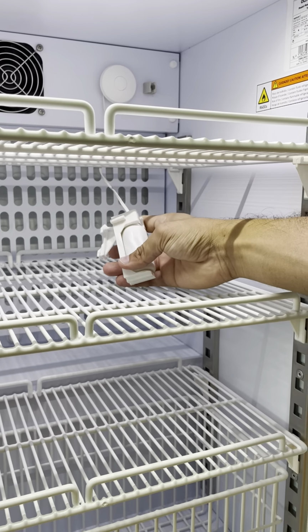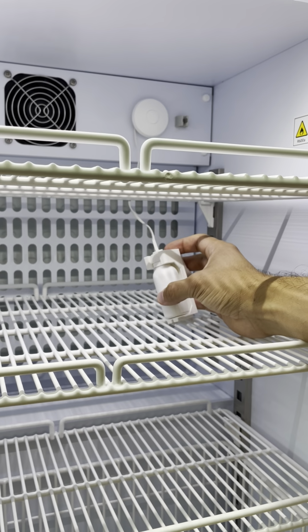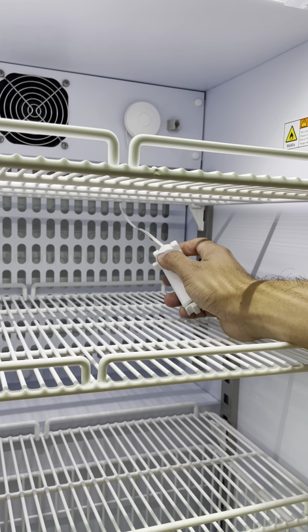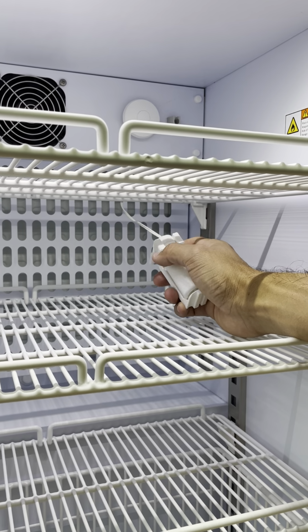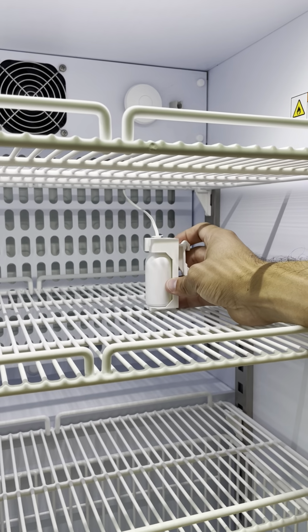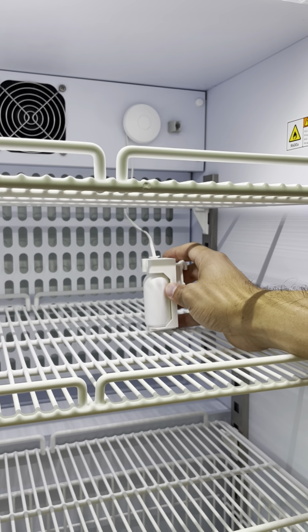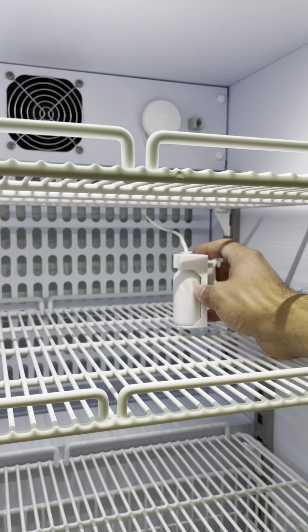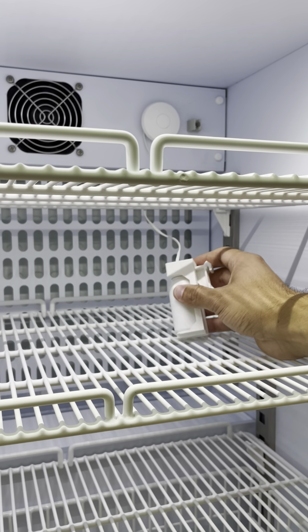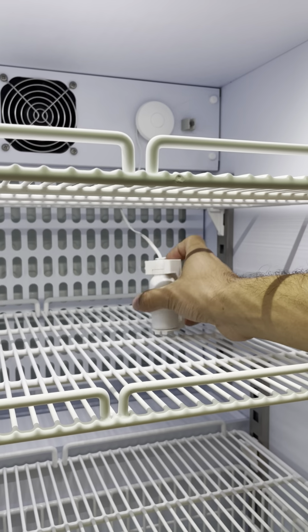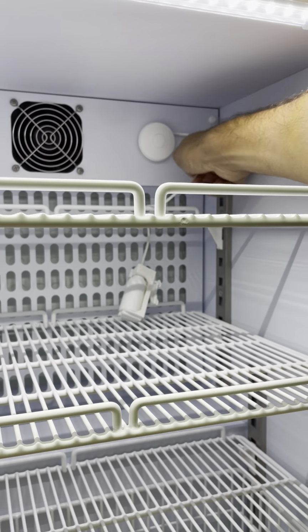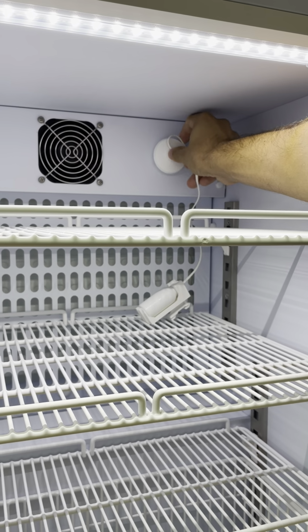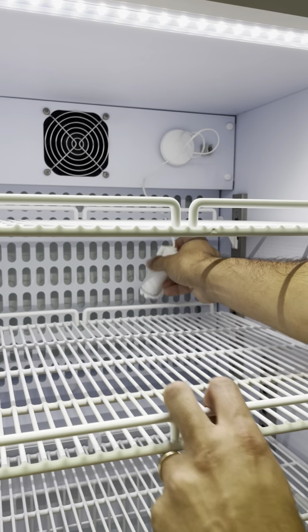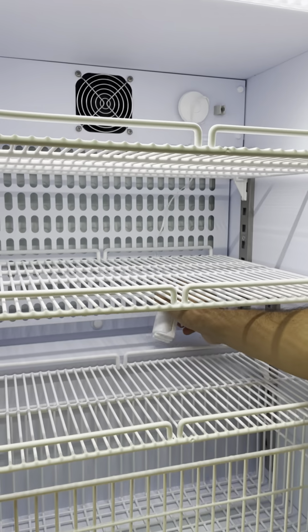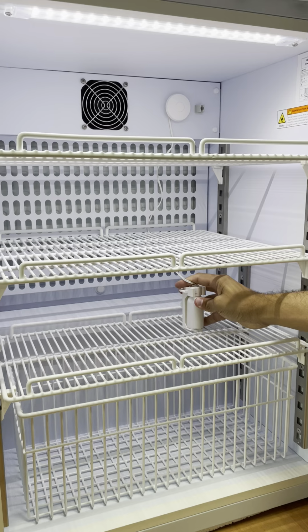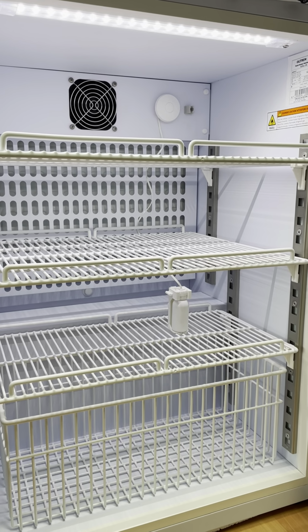So this simulates the product temperature, meaning, of course, when you open the door, the temperature of the air goes up very high, very quickly. This is a simulator of a product, so it simulates a box of medicines, and this gives you the real temperature that the medicines can reach when you open the door. So this is more accurate than the other. You can put it in any place. You just unroll the cable, and you can put it anywhere in the equipment. Imagine if you want to measure the temperature in one exact place of the equipment, you just do like this and you fix it, and you can know that.